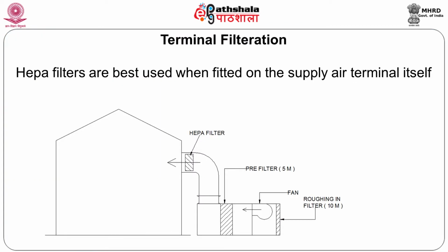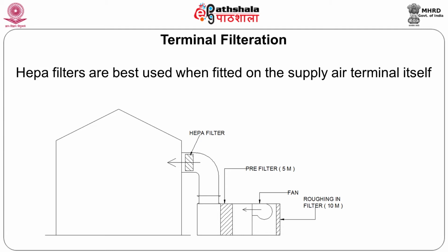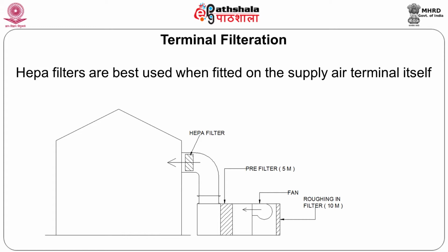So invariably what is done is you look at using HEPA filter as a terminal filter. Terminal in the sense that not fatality, terminal in the sense that it is used at the terminal of the air duct. So you would have noticed that in this slide you see the HEPA filter moved right up to the point of entry into the space of interest. So upstream, that means in the machine, you might not have used the machine for a week, some vermin might have bred, it might have left some bacteria, virus, it does not matter because it will get caught on the terminal filter.